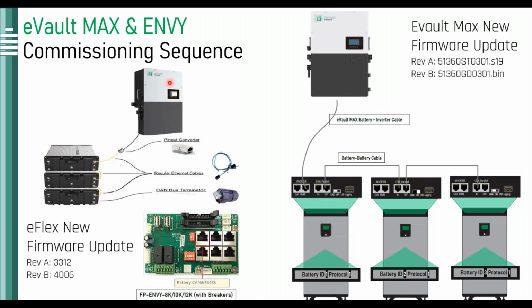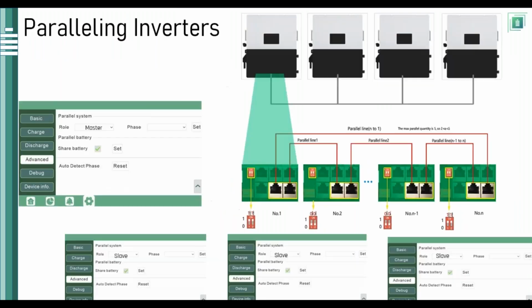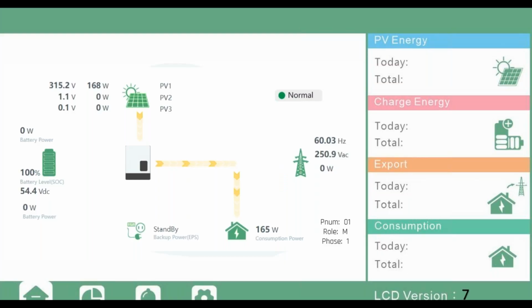Once your system boots up, assuming that your battery breakers are also on, then we begin to commission the system. You will always start with the DC, turning on your battery, then your PV. Once we set everything on the LCD, we always recommend putting the system in standby before proceeding. And then I'm going to go ahead and explain what the remaining steps are.